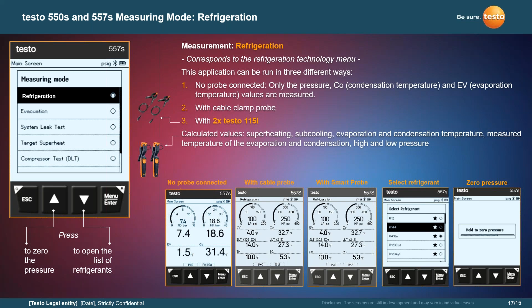You can also zero out the pressure on these, and it's recommended every time you use it. So going into evacuation, you've got a target entered there. You can set up alarms for you to know when you hit that. So if you're multitasking, again, this is external. You're connecting this to the unit or to your core removal tool to get those readings. And then you also have a decay target that you can put on there with alarms to help let you know when you reach that threshold.